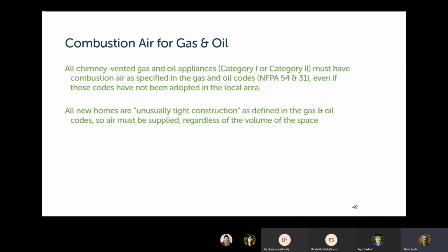Also, those codes use a phrase called unusually tight construction, and they say, that is NFPA 54 and 31, the National Gas and Oil Codes, they say that things change when you are dealing with unusually tight construction. The Vermont Code specifically makes clear that any house that meets the Vermont Code is unusually tight construction as defined in the gas and oil codes. So it's not really unusual at all, it's usual.